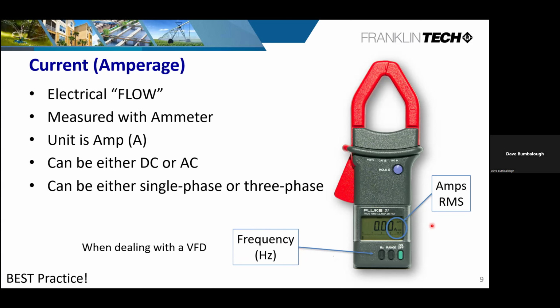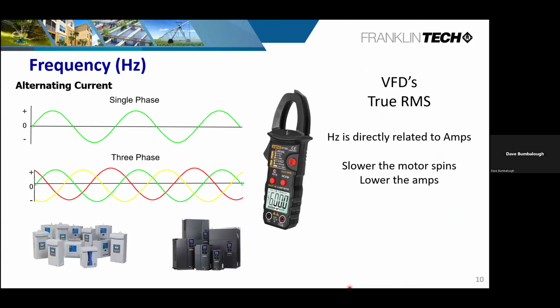So until it's at full speed or its rated speed, the only amperage that is published is typically its nominal speed amperage. So going forward, what I would suggest is that your meter have that functionality, and usually the clamp-ons are the best. To go one step further, true RMS, root mean square, is how it looks at the sine waves that are coming through the system. We want to make sure that we're measuring the peaks without any kind of transients on there, so it's basically taking an average. But the most important thing is, at 60 hertz, that's where our rating is going to be for the amp draw of that piece of equipment.